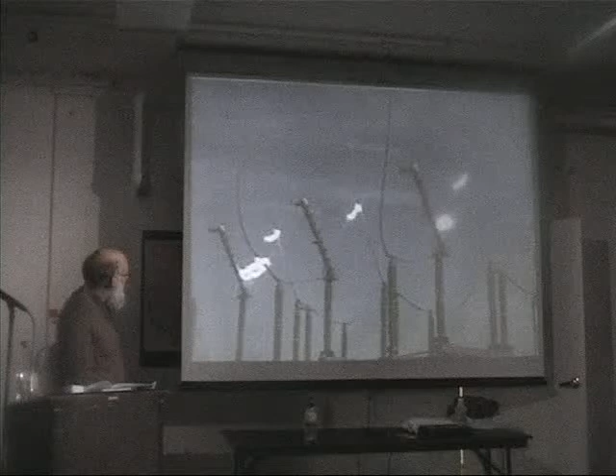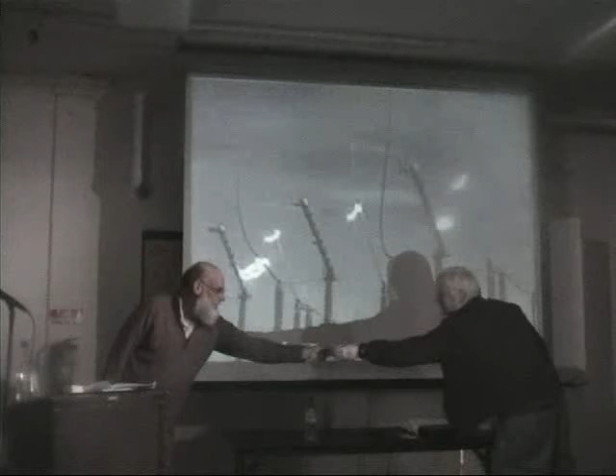We're trying to turn off a 220,000 volt power line. This is the switch, it stands about 50 feet high. Now what they've done is, in order to eliminate the oil tanks which normally break the discharge, they're using vacuum columns. The mechanism breaks the circuit inside the vacuum columns. But being that there's no gas or oil or anything to carry the current through to the zero part of the cycle, the voltage tends to raise to infinity, trying to maintain the power flow.